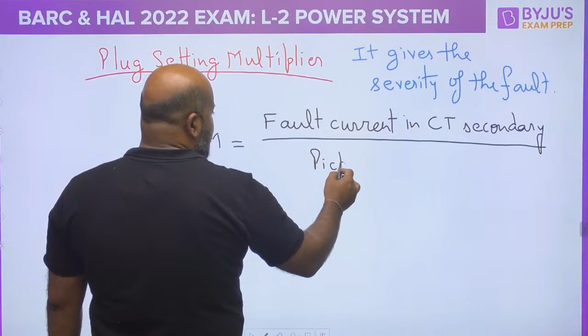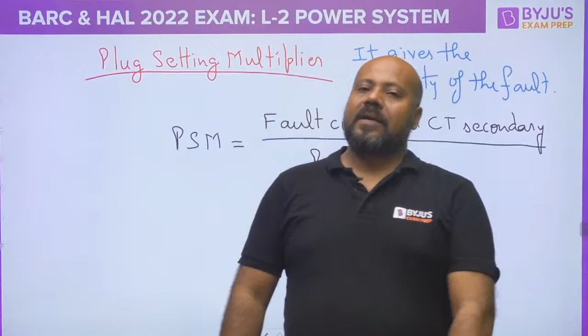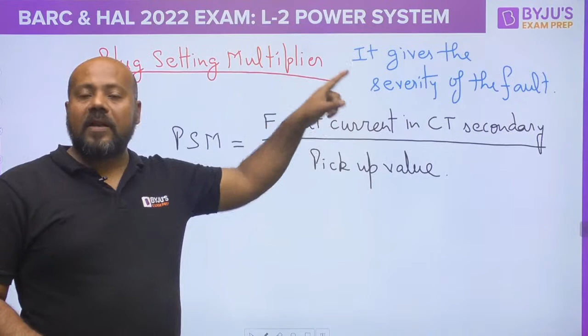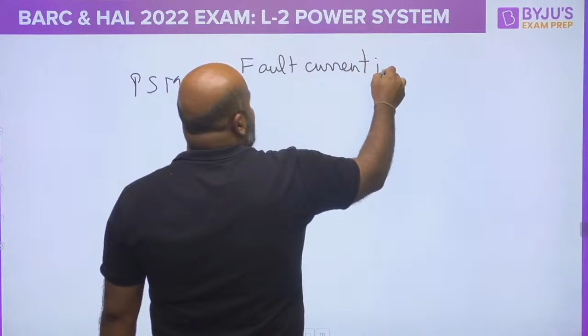So you can just write it as, this is going to be the fault current in CT secondary. If you know the relay operation, circuit breaker operation, then you will be able to understand why I am writing CT secondary. Because we are taking the sample of the current from the line, and the line itself works as the primary of the current transformer. So whatever current sample we are taking, that is going in the secondary of the CT. Now this current we are comparing with the reference, that is the pickup value. Actually this is the basic expression or formula for the plug setting multiplier.